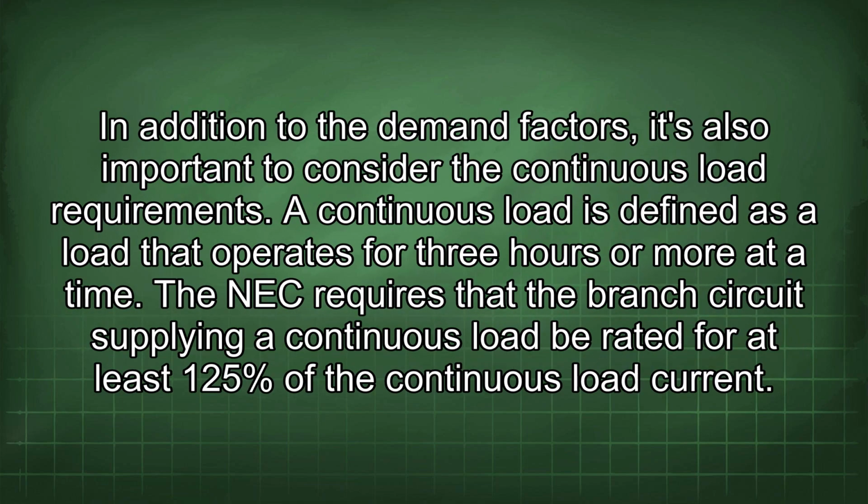In addition to the demand factors, it's also important to consider the continuous load requirements. A continuous load is defined as a load that operates for 3 hours or more at a time.